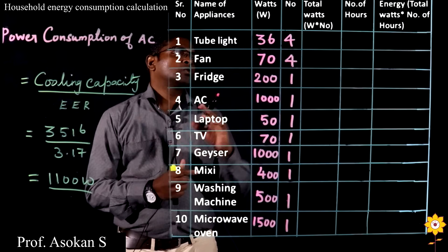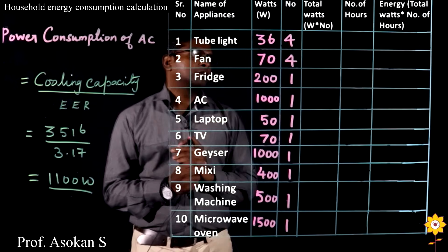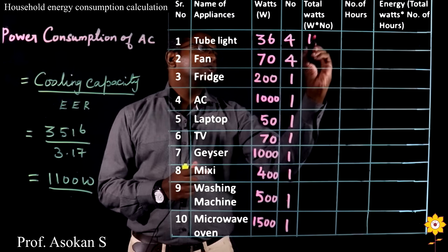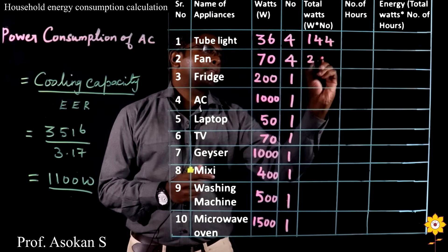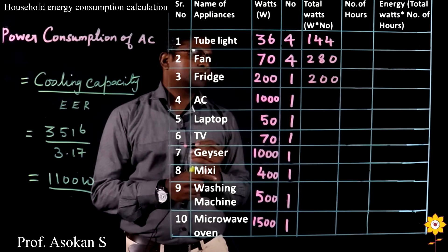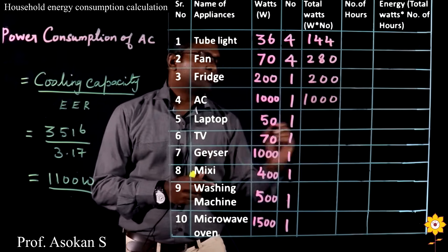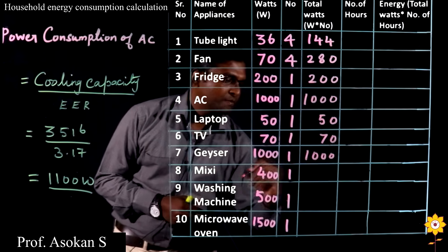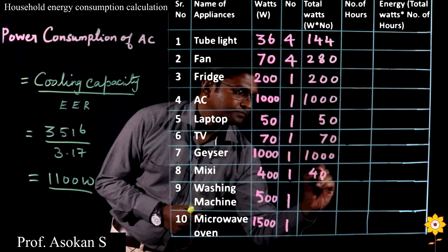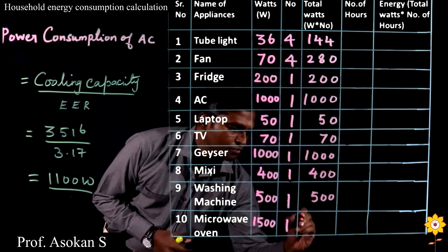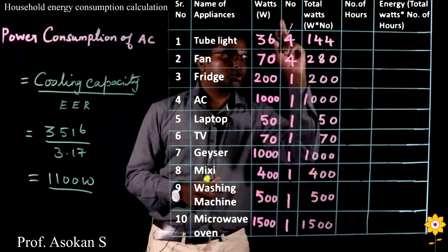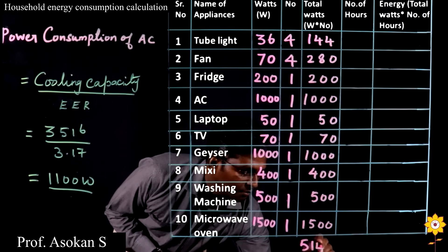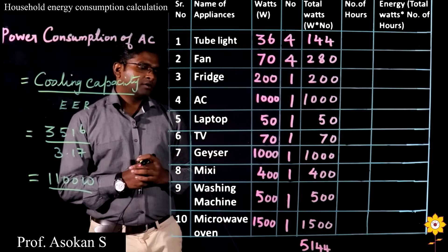Then we calculate total watts — how many total watts are consumed by each appliance. For tube light: 36 Watt multiplied by 4 units equals 144 Watt. Fan: 280 Watt. Fridge: 200 Watt. Then multiplying through: AC is 1000 Watt, geyser 1000 Watt, washing machine 500 Watt, and microwave 1500 Watt. So the total power absorbed by all the home appliances is 5144 Watt.